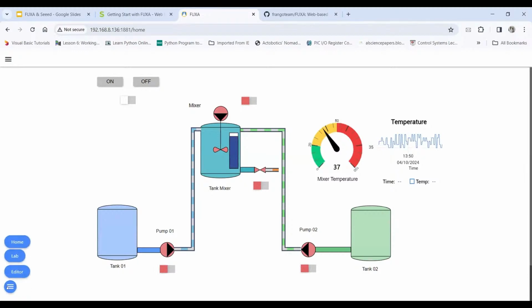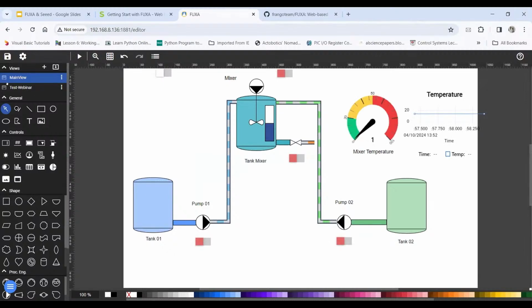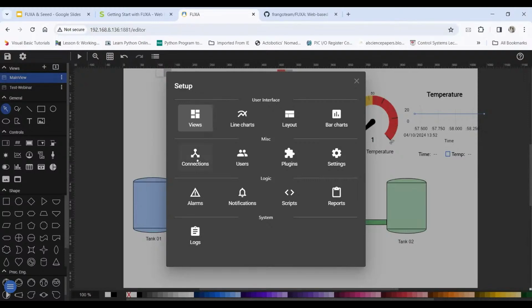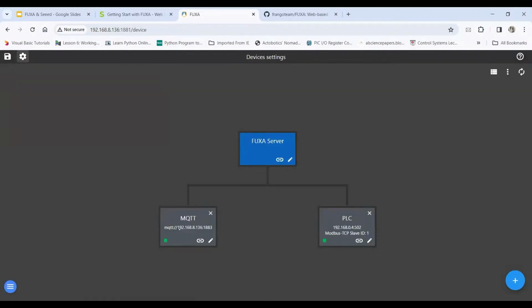Let's go to FUXA, and I'll demonstrate how to add these things. Go to editor, and here you can see the settings. Edit projects, select connections, and you can see I have already connected two devices, my MQTT server and my PLC. The green light is blinking because the connection is already established well. If you want to add a new device, you can simply click this plus button.